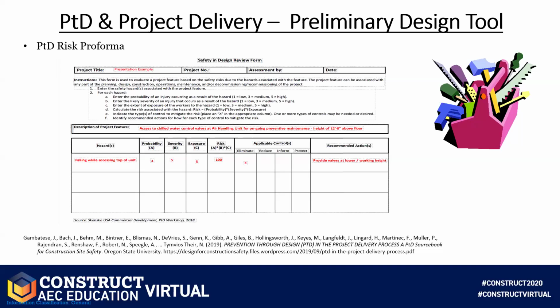Let's take an example from an actual project I had. In a utility plant, there were several chilled water control valves for some air handling units that would require occasional preventive maintenance, access to make sure they're operating correctly. But they were very high up, above the air handler, probably at least 12 feet off the floor. This was caught in design, and one of the hazards identified was falling while accessing the top of the units to get to the valves.